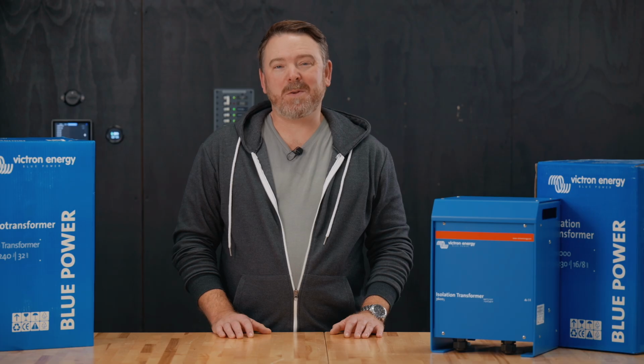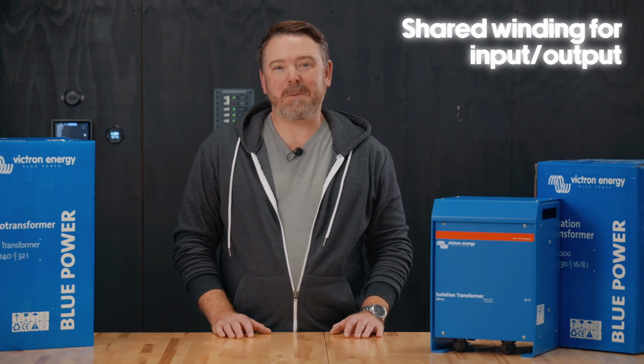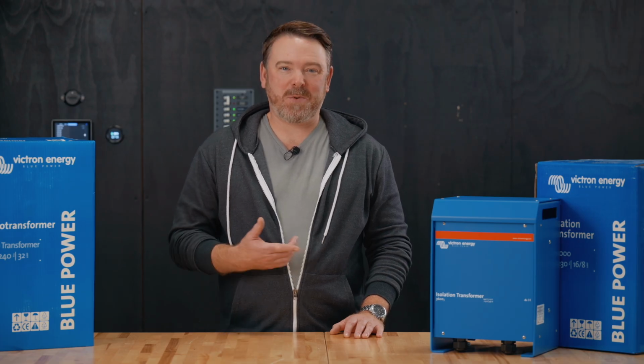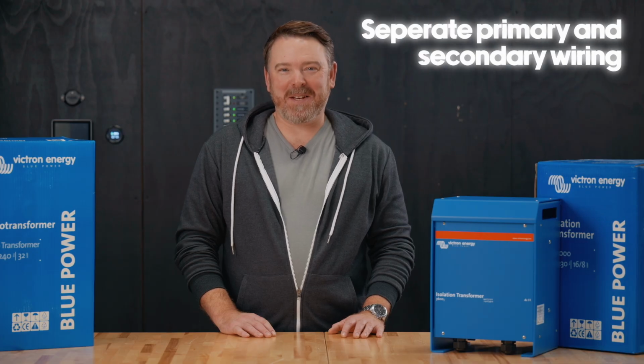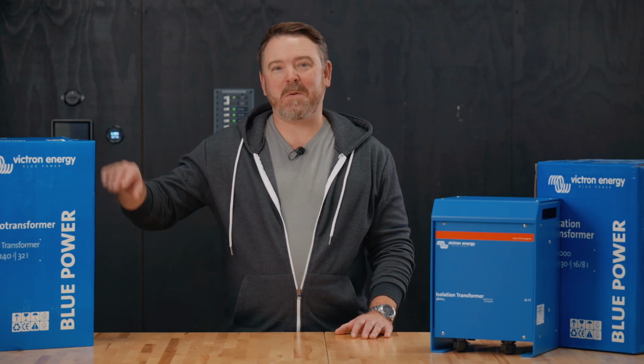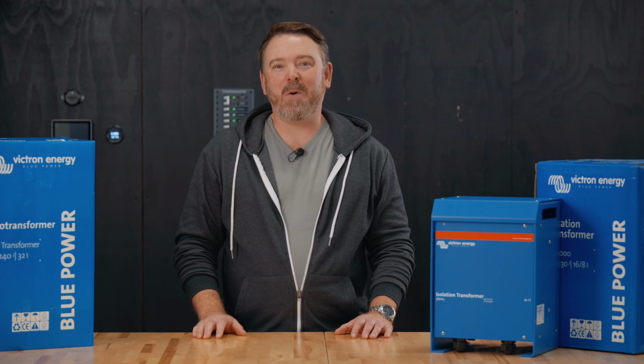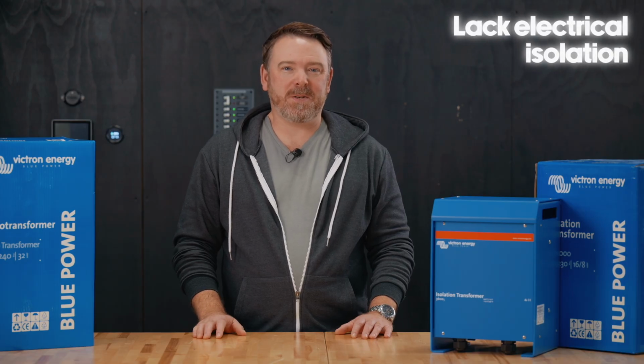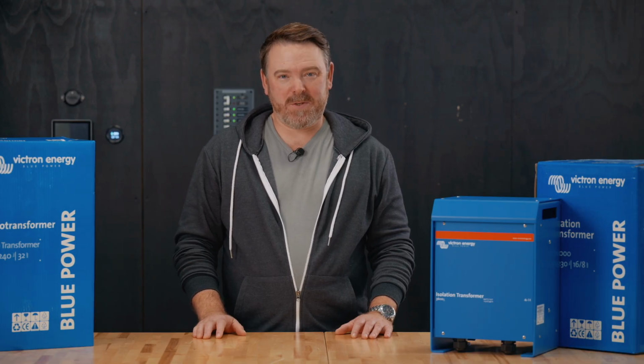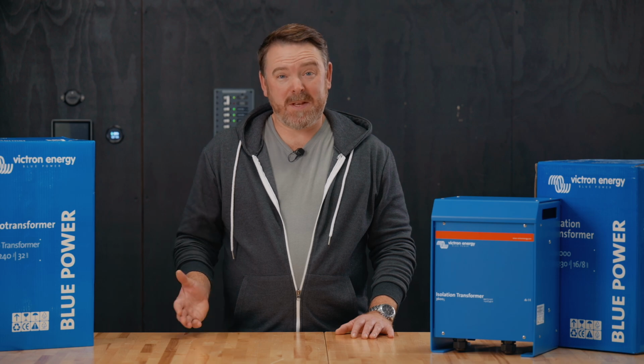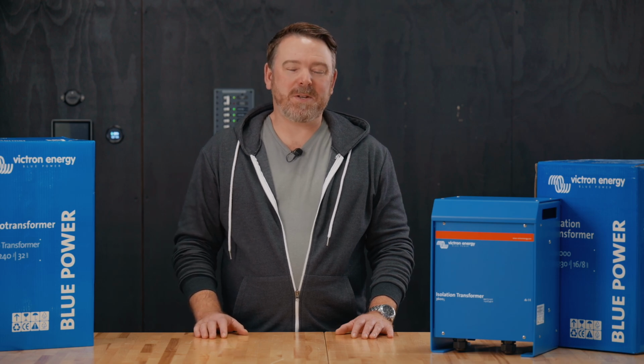This is a question that comes up, and it's understandable given that they're both electrical transformers. Let's run through what makes them different, the key features of each, and common installations where they're needed. An autotransformer uses a single shared winding for both its input and output, while an isolation transformer has separate primary and secondary windings. This means autotransformers are typically smaller, cheaper, and more efficient, but lack the electrical isolation and safety benefits of an isolation transformer, which is ideal for applications where physical separation between circuits is required.